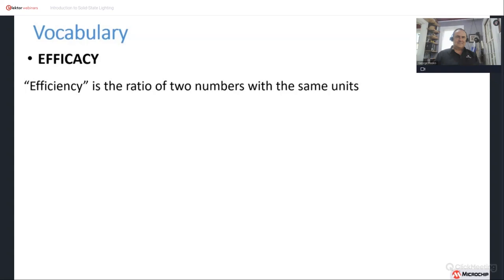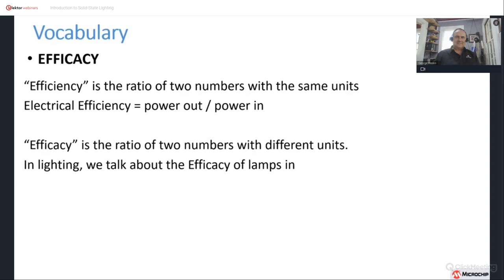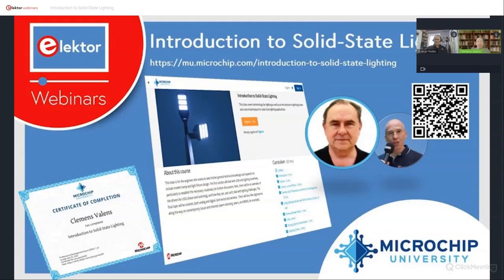The next word is efficacy, and we'll start by saying what it isn't. Efficiency is the ratio of two numbers with the same units — in the electrical world, electrical efficiency is power out over power in. Efficacy is the ratio of two numbers with different units. In lighting, we talk about the efficacy of lamps in lumens per watt — that is, the human-weighted apparent output of the light per electrical watt in.